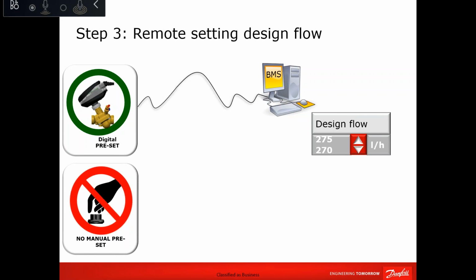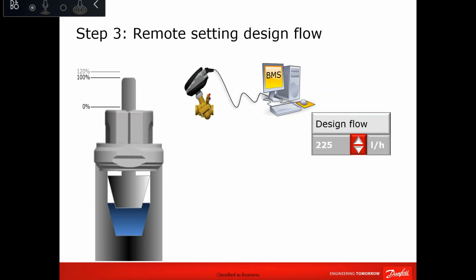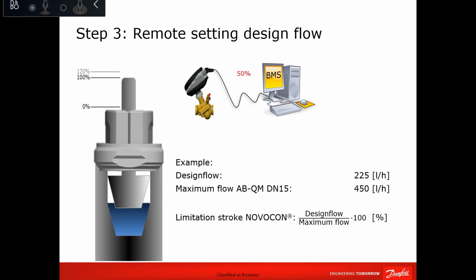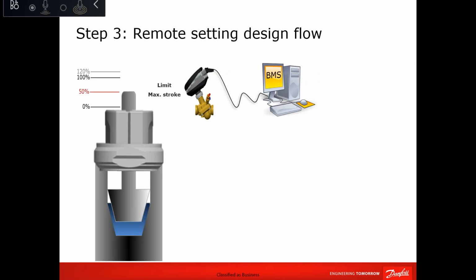Remote flow setting. This is a very nice feature, I would say. Instead of doing the manual presetting, which leaves more room for human error, remote flow setting will remotely assign the maximum flow that will be modulated. So in our case, the valve is DN15 with a nominal flow of 450. The setting of the flow here is 225, which is 50%. So once you have this, you just feed it into the actuator, and then it will limit to 50%. Now the 10 volt or the 100% will be that 50%. So why do we say this? Because since you can do this for one valve actuator, it can also be done for the whole loop.